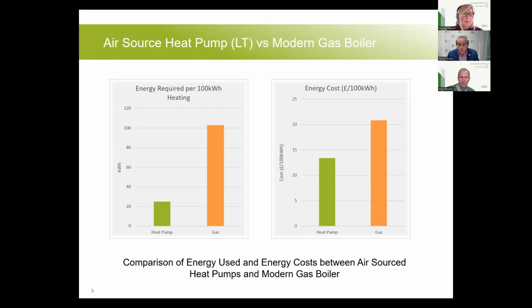If we use the costs from my office in October 2022, we can now see that with a COP of 4.5 at that condition, the cost drops down to 13.4 pence compared to the 20 pence we had before. So in these instances, you're starting to see real savings from running an air source heat pump in these extreme lower temperature conditions. And we're also using a lot less carbon as well as it being cheaper to run, so hopefully it's a win-win.